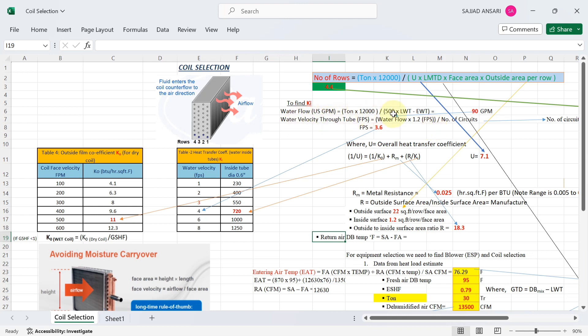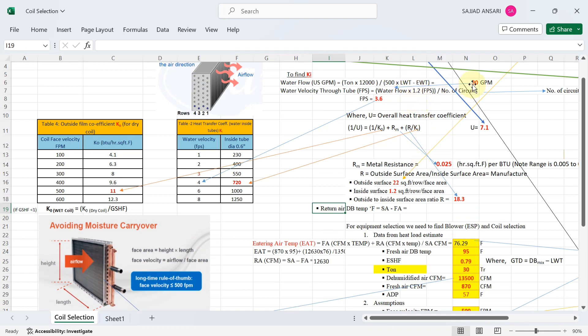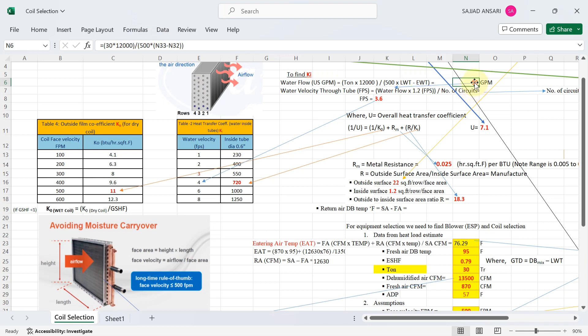To find the water flow value, the formula is: TR × 12,000 ÷ (500 × (leaving water temperature − entering water temperature)). Leaving water temperature is 52°F and entering is 44°F. When you apply this formula in the sheet, you get 90 GPM water flow.